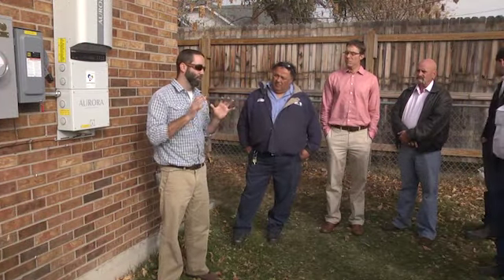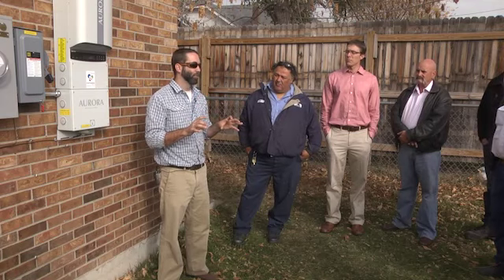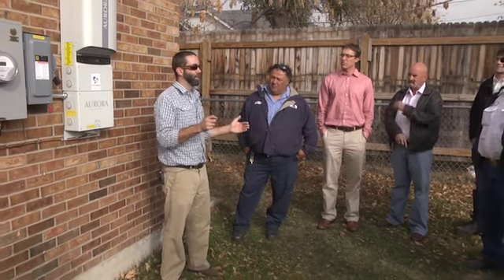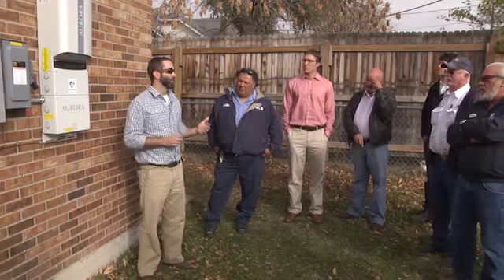If I'm just working on one circuit in a bedroom, say a lighting circuit, and I've already turned that breaker off and I'm replacing the outlet, chances are good you'd be safe in that situation. But best practice: get in the mindset that any time you're doing anything electrically in this unit, turn the main power off as well as turn the solar off. It'll only be down a short time. Replacing a receptacle or light socket isn't a huge amount of work. You want to communicate that to the resident, but that's a safety issue - that's how I would do it. Belts and suspenders sort of safety thing.